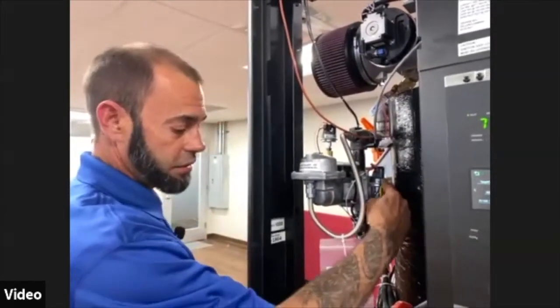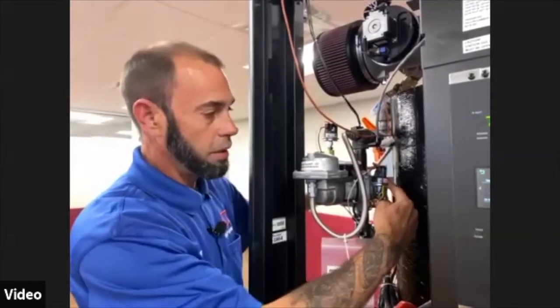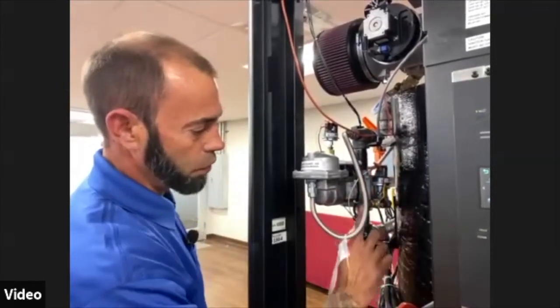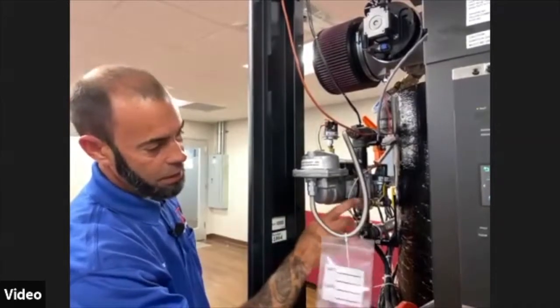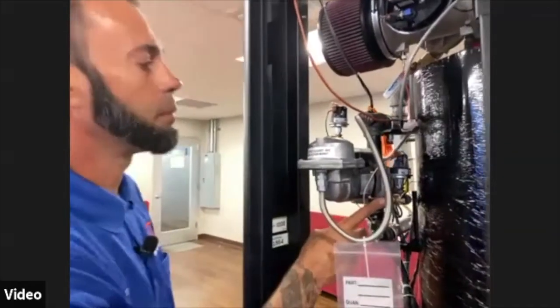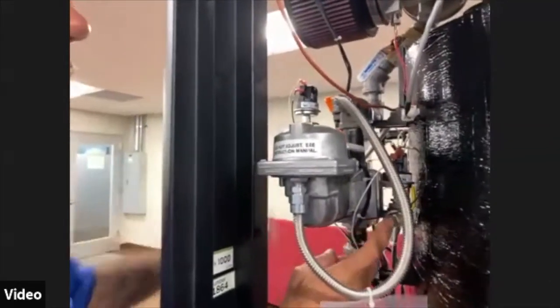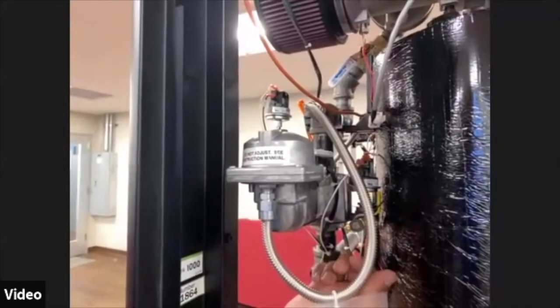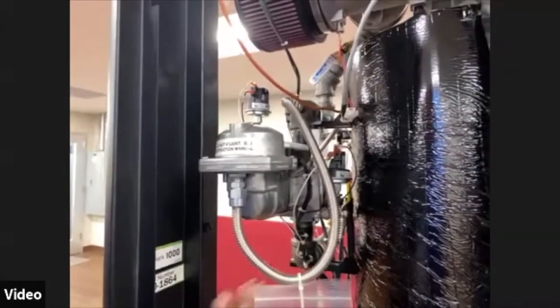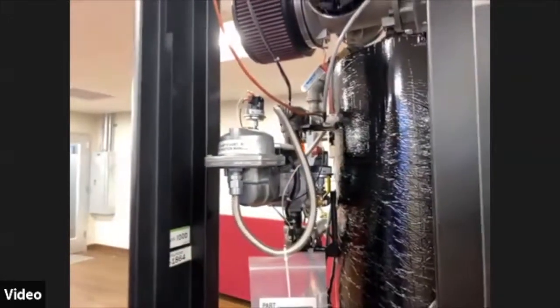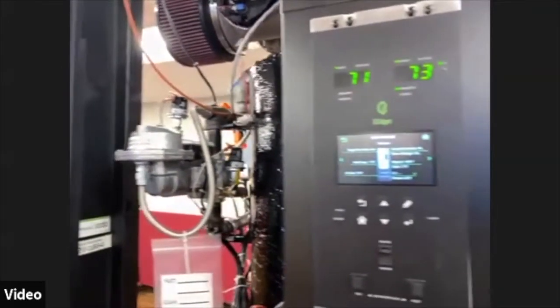The way you can test this device is to simply start closing off the gas valve with a manometer hooked right here. Take this plug out, put your manometer in here. Slowly start closing off the gas. As it drops and gets below 2.6 inches, the switch will open and the boiler will shut down on a gas pressure fault.